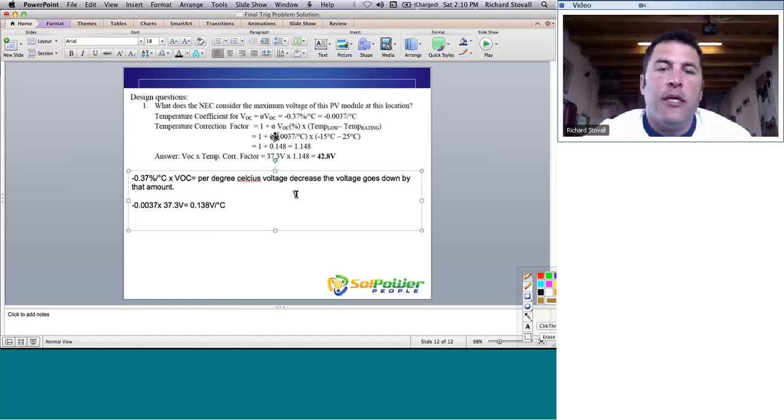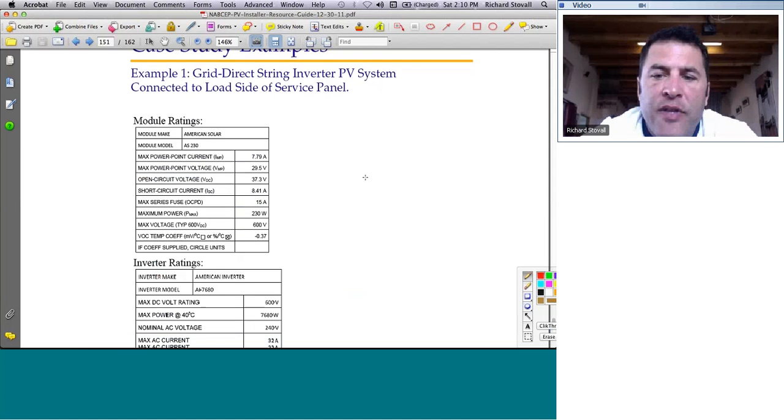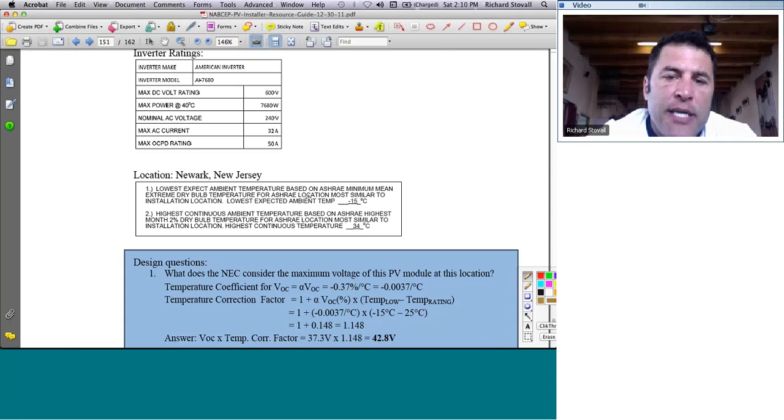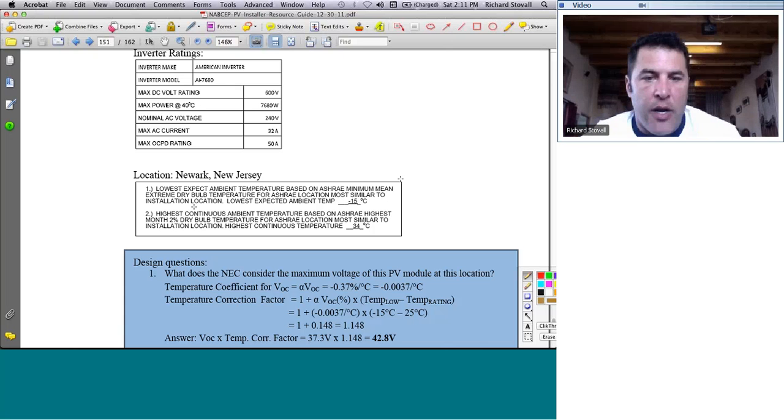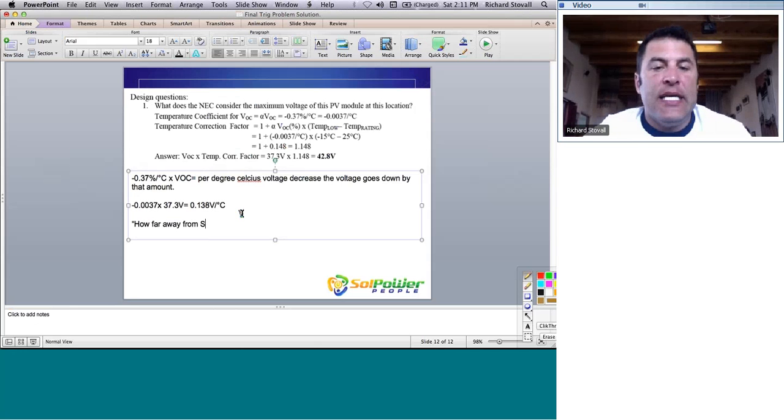Okay? So the way I like to look at that is, if you go back here, we're given the guidance. The lowest expected ambient temperature based on the ASHRAE, which is the American Society of Heating, Refrigeration, and Air Conditioning Engineers, minimum mean extreme dry temperature for the ASHRAE location most similar to the installation is negative 15. So ask yourself the question, how far away from STC is negative 15?